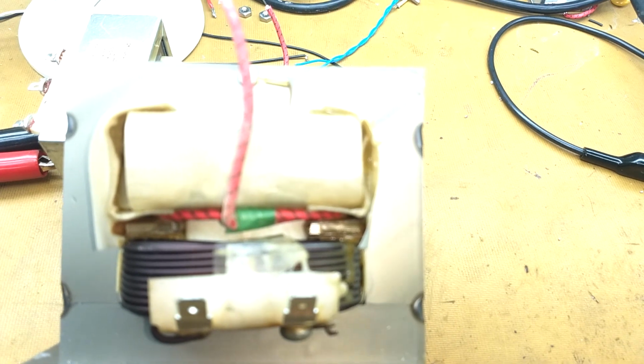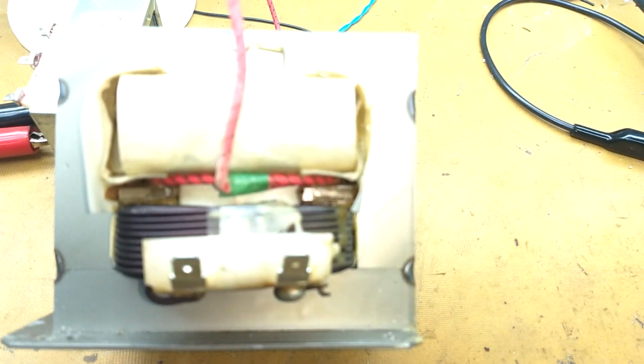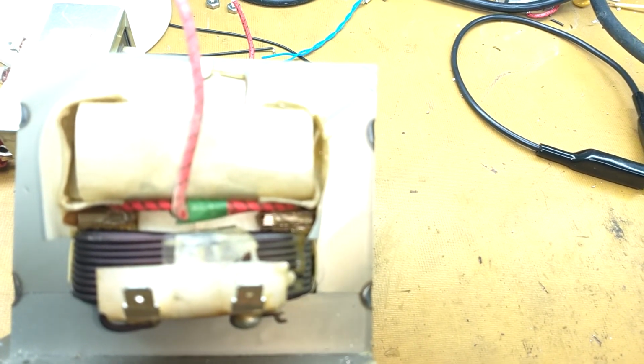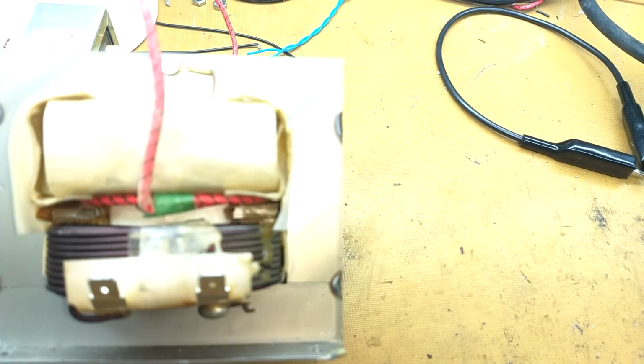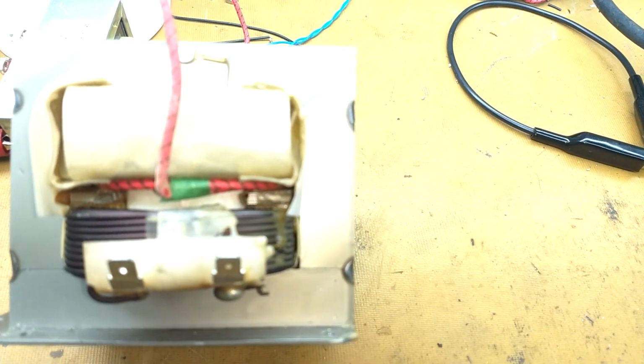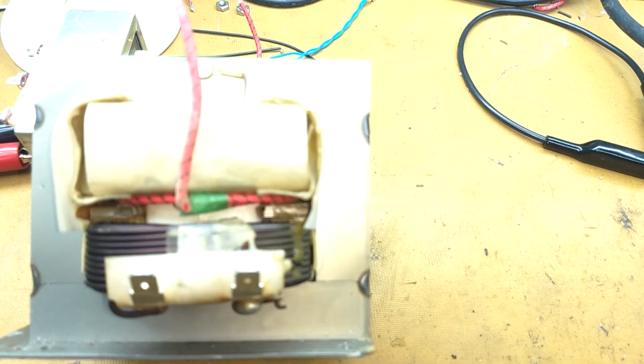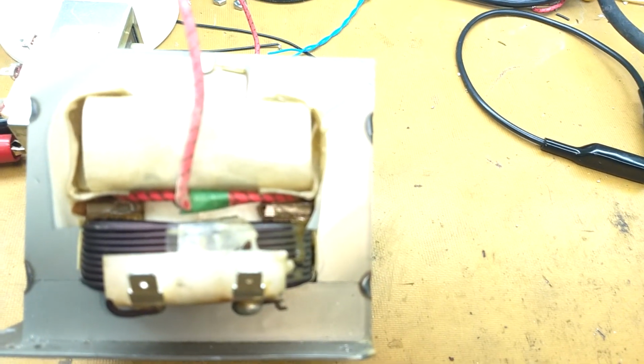Now, this little stack of laminations can be removed. You can just drive them out with a hammer and a wooden dowel. But you'll find then that the primary current under no load goes up even higher. So you would need to add turns to that primary to keep from saturating the core. If you intend to build this into some other device, like if you want to make a little welder or whatever, you'll have to take care of that situation.